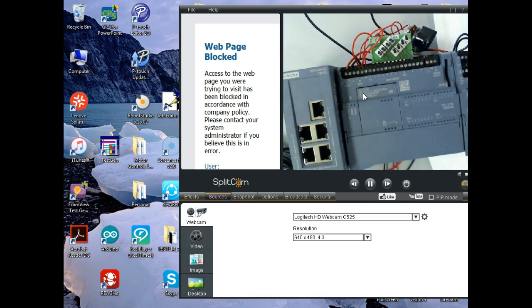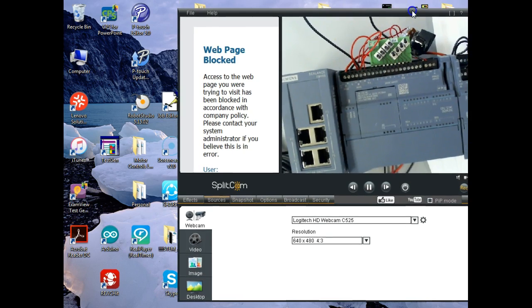So even the Compact Logix that we have, which is the next version up, they have these removable terminal boards too. So it makes it a lot easier for the technician to swap out a PLC instead of having to rewire it. That used to be the problem with relays, is that we had to replace a relay, and it's got 15 contacts on it. What did we have to do? We had to rewire the whole thing. And that's where you got into problems. People would start wiring it and they'd do something and they wouldn't keep a document of what they did.